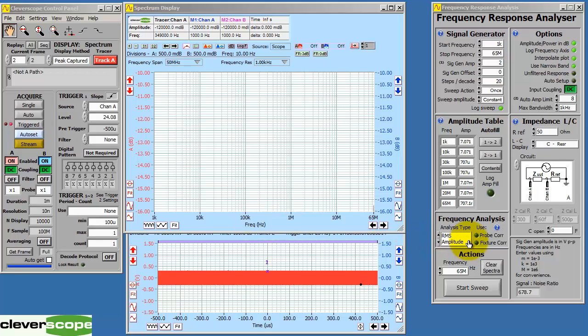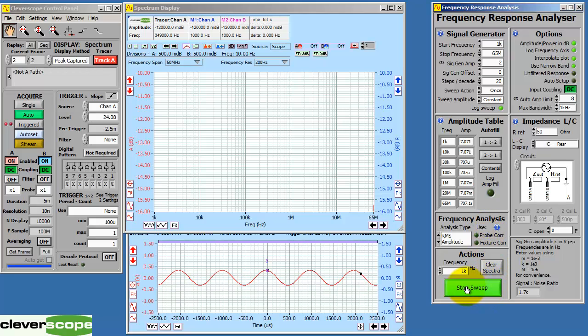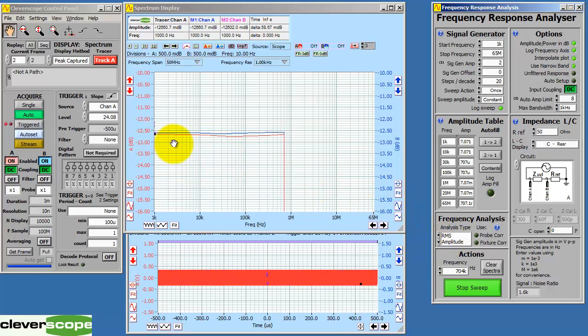Here we have the two probes again connected together in the BNC jig with a frequency range of 1 kHz to 65 MHz. We leave probe correction off. We start the sweep. We see an RMS level, we've set the RMS amplitude, of about minus 12.5 dB. As you can see, as we get up in frequency, it starts falling off. This is the frequency characteristic of the signal generator.